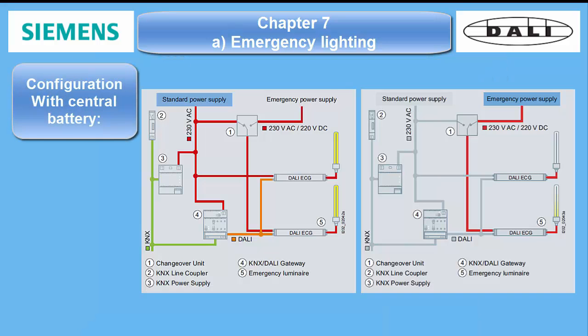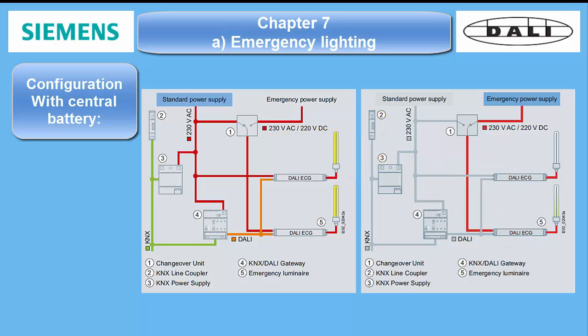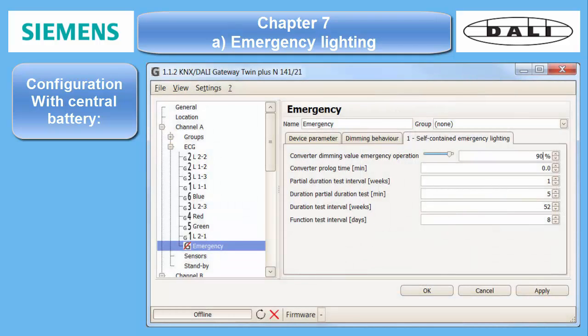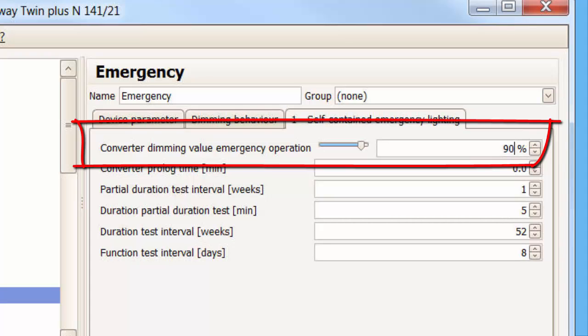2. Configuration with central battery operation. As mentioned before, all DALI ECGs support the safety lighting option in general. That means if the control line — the DALI bus — doesn't operate anymore, which usually happens when the main supply for the DALI gateway fails, the ECG will switch into the so-called system failure level, if it is still under power from safety power supply. All the system integrator has to do is set the required light level parameter in the ECG's options.